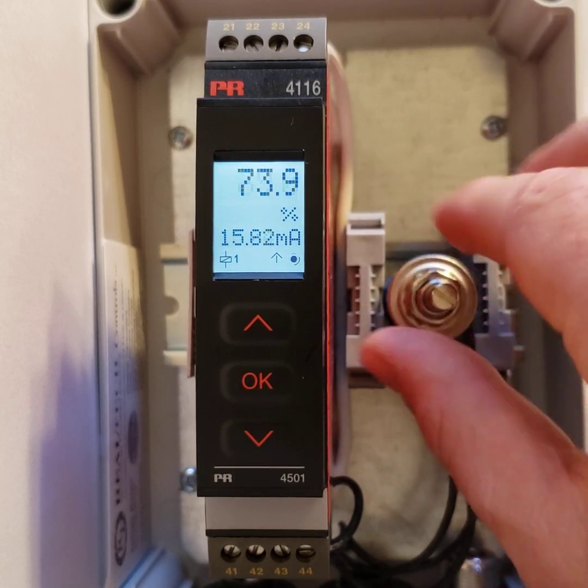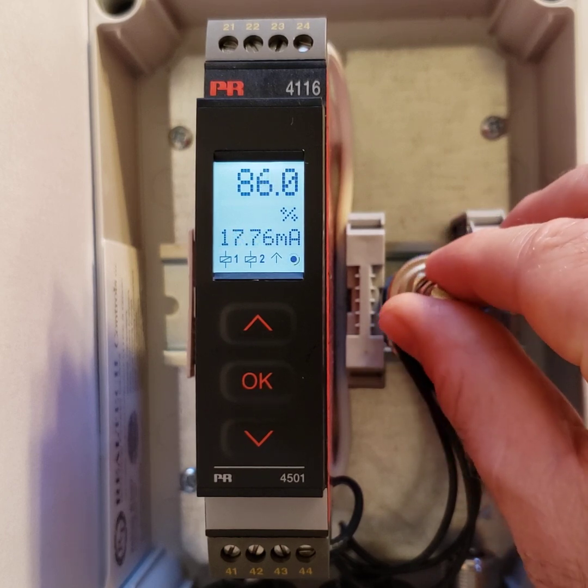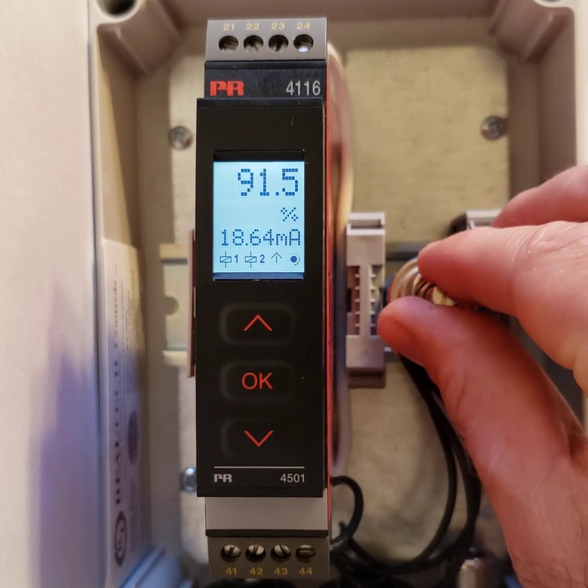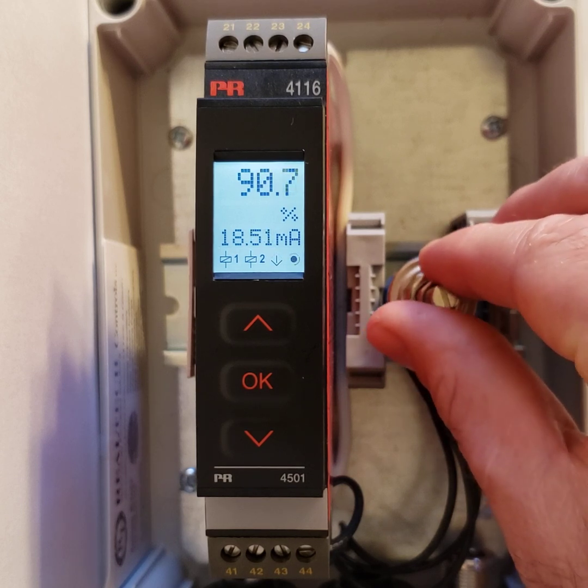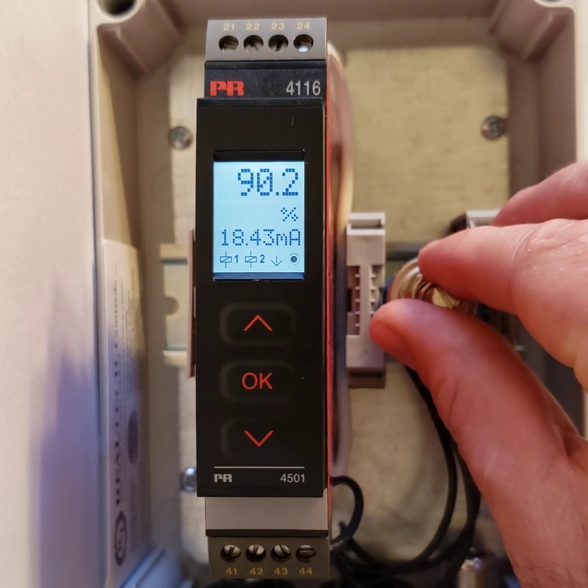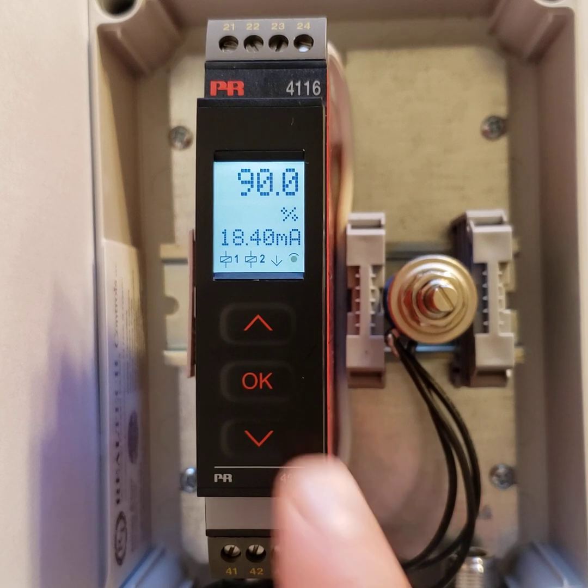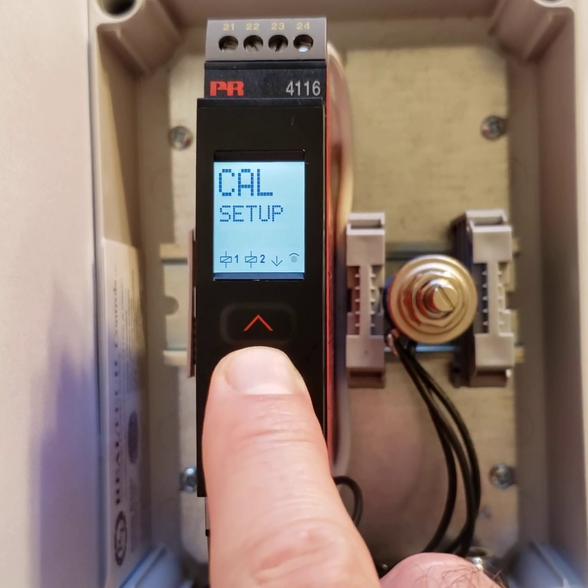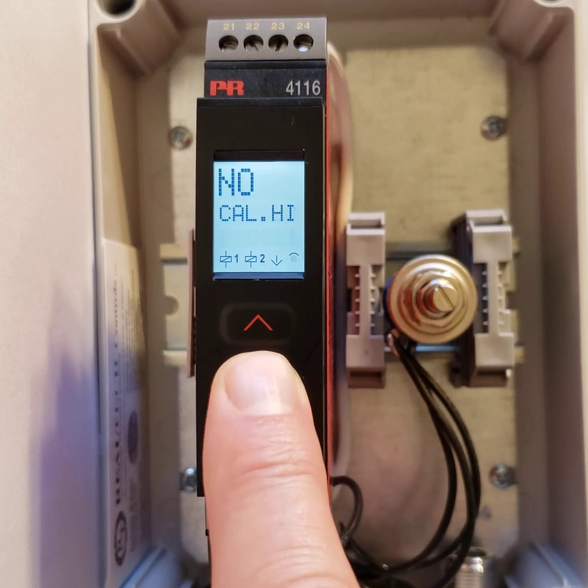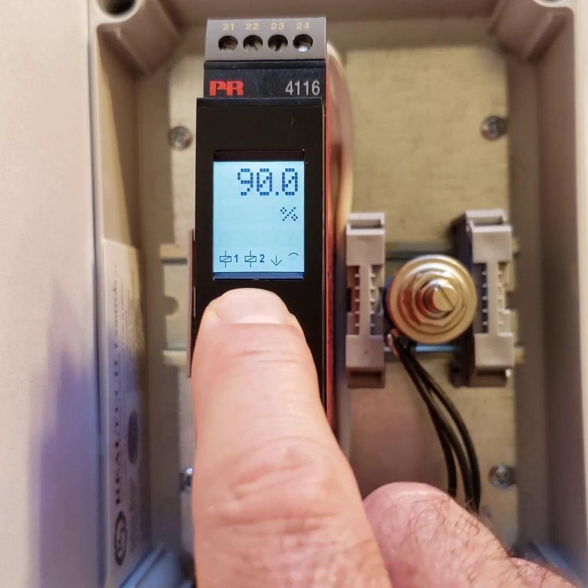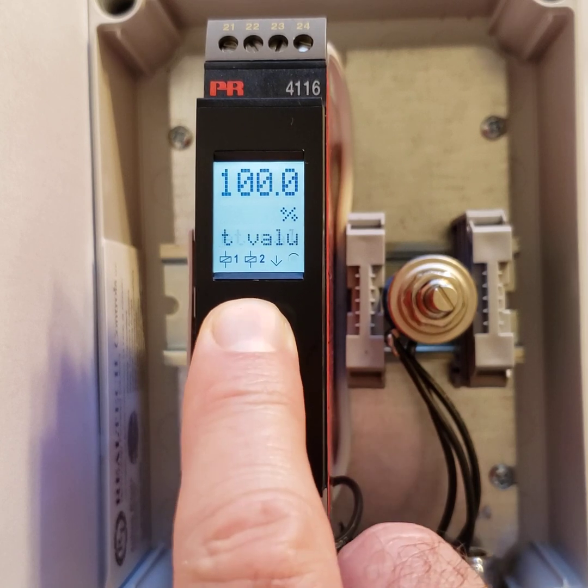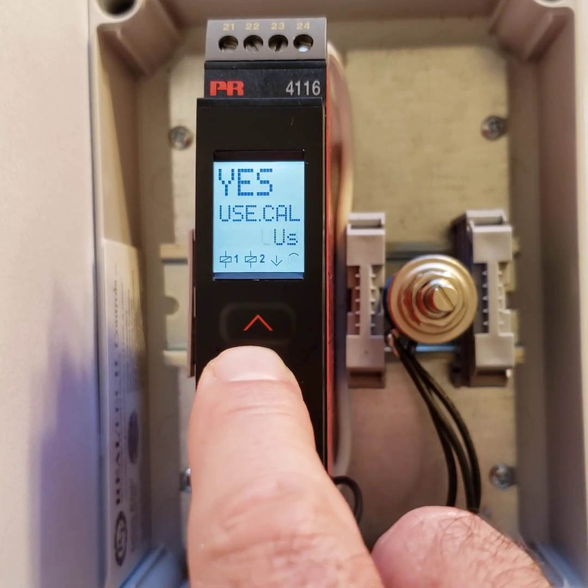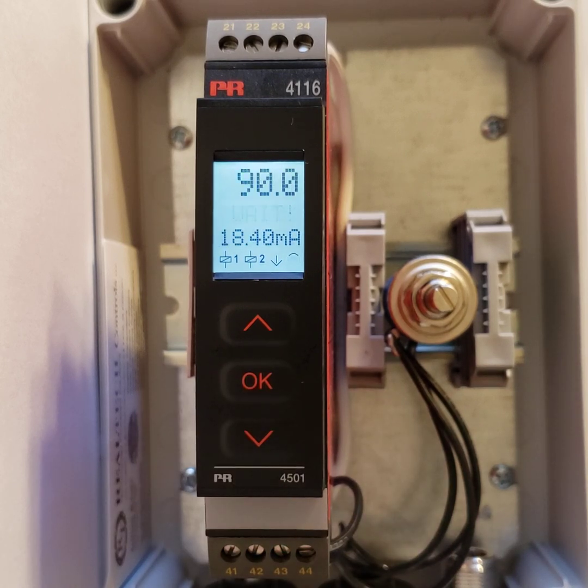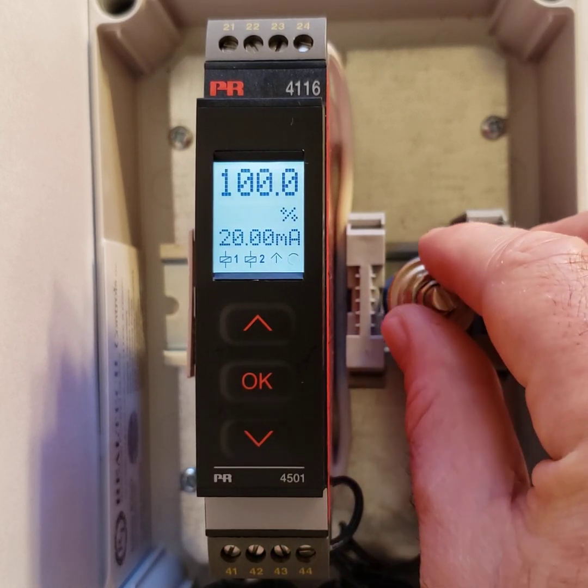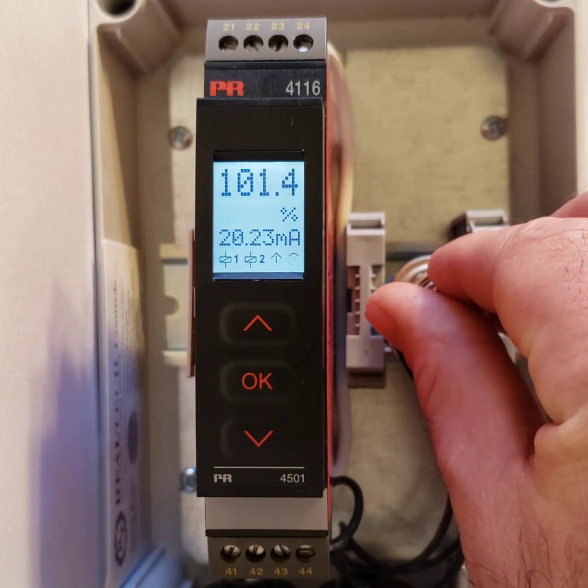And say my full value of my tank or my process is 90%. But I want this to show 100%. So I go into my calibration again. I don't want to calibrate my low. Now I want to calibrate my high. And I want to adjust that now to 100%. Calibrate. Use calibration. Yes. So now you'll see that when my pot is 90, it's still going to be 100%. If I go over, you can see it go a little bit over.